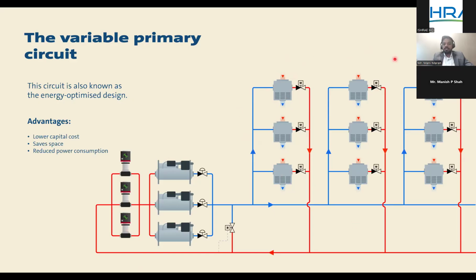And as I said, this system is a pressure-driven system. So when there is a change in flow based on the movement of the valve, the back pressure at the critical load or furthest loop is monitored, and that is given as feedback to the pump to move the flow up and down. That's how we understand the change in load on the secondary side, and we give pressure as feedback to the primary pump to modulate the flow and manage the demand by exactly producing and driving the flow from the primary side.